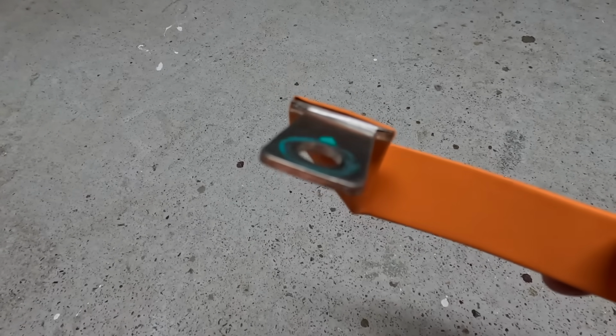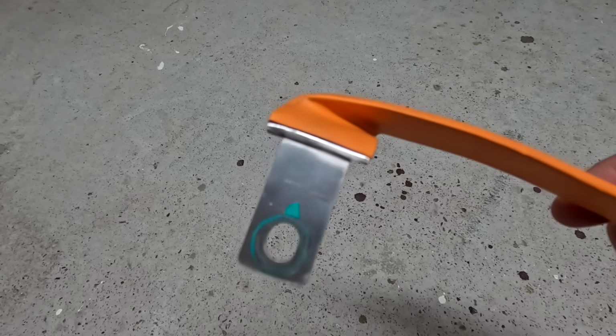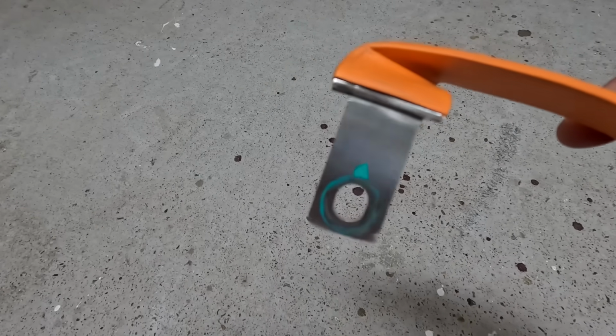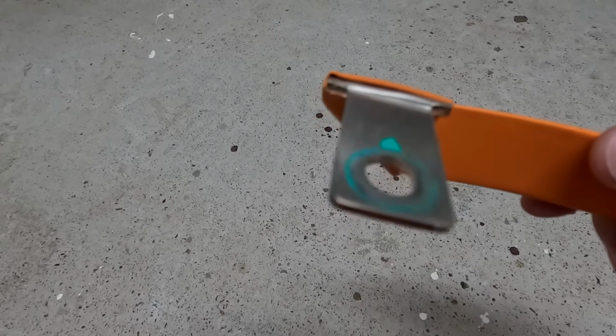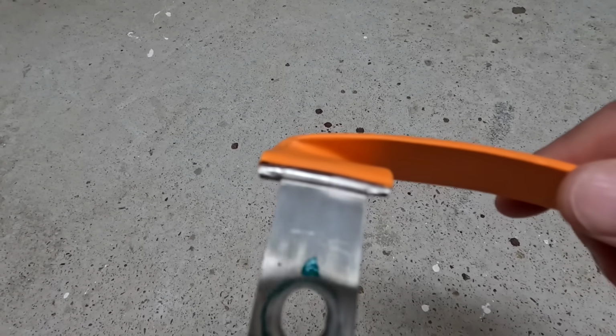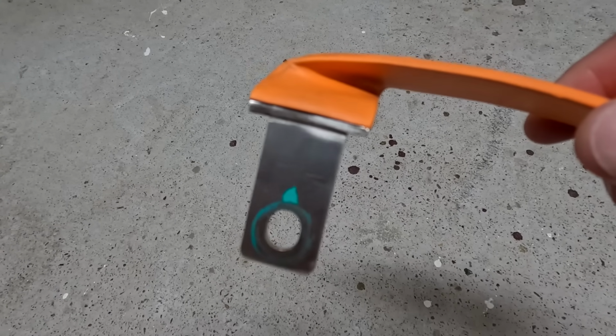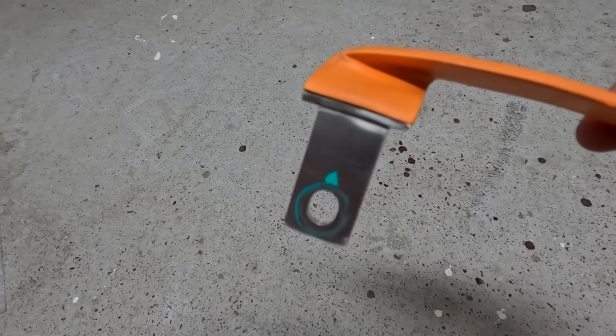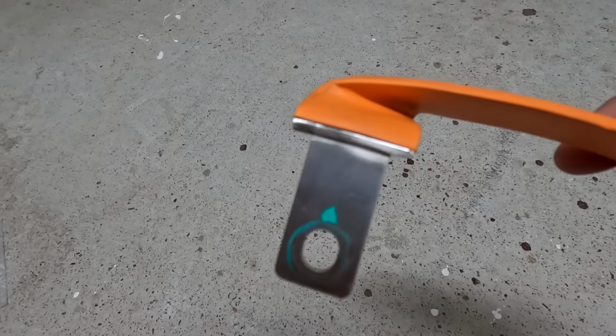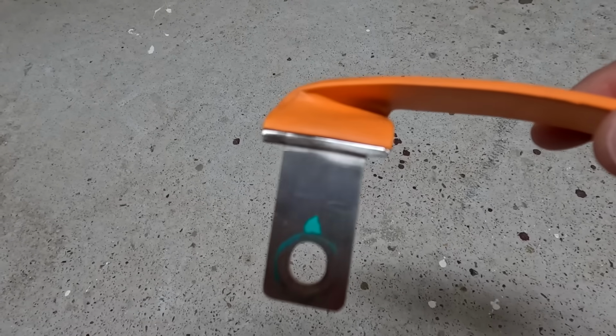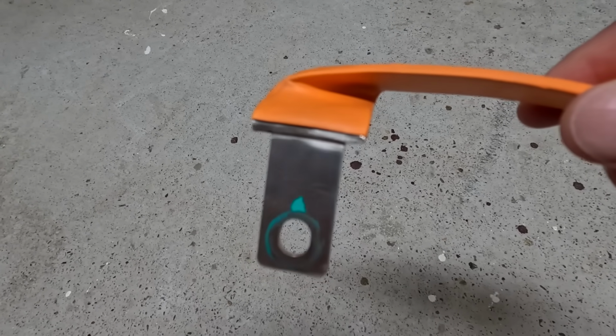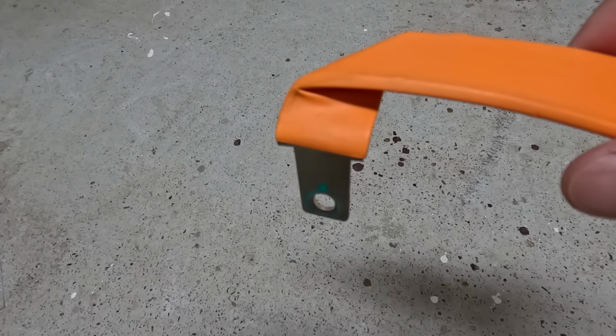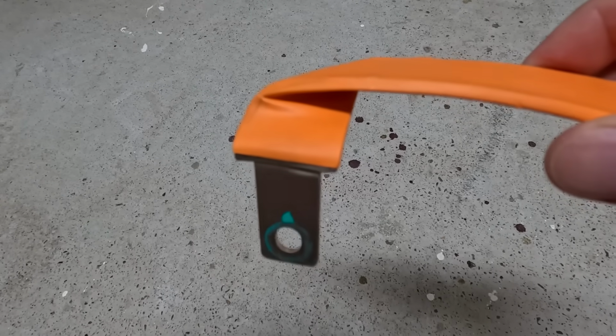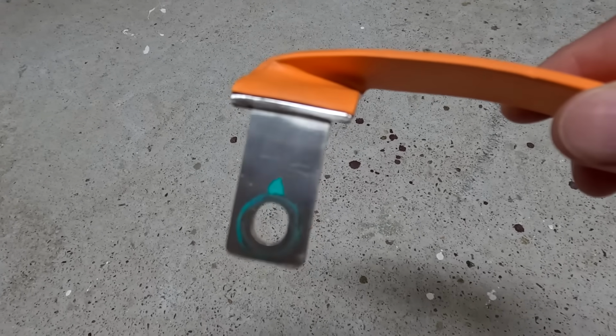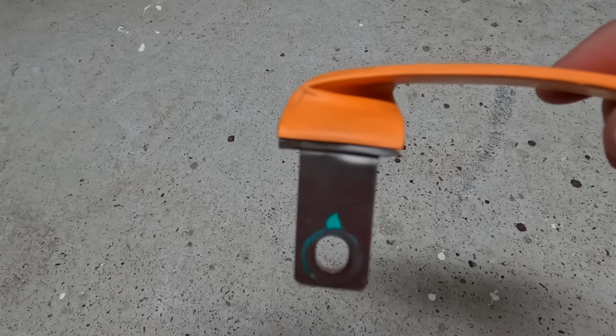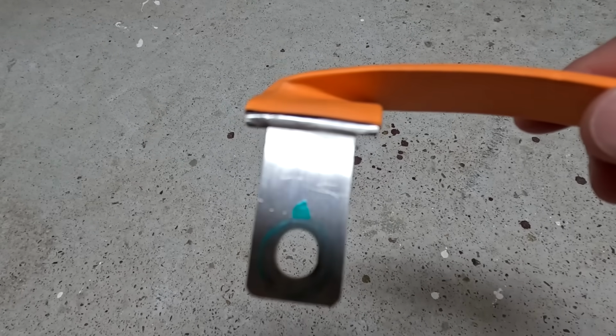This is exactly my complaint again. I think we flagged this before, and they modified the bus bars so they are not cut like this one. What they have done here is reduce the physical diameter of the bus bar, cutting away a bit left and right to make it fit into the circuit breaker. But this isn't okay because we're reducing the diameter of the conductor, so this is not a 200 amp bus bar anymore, maybe only 150 amp now.